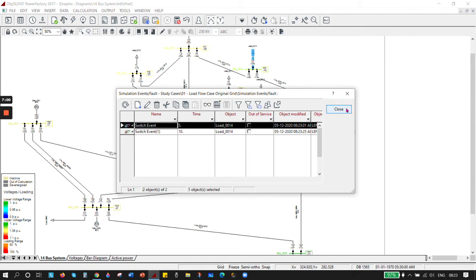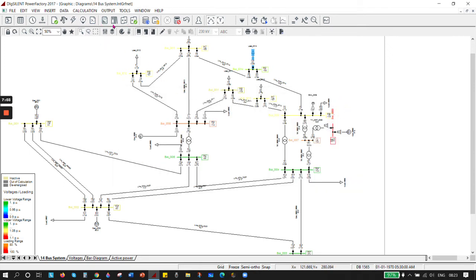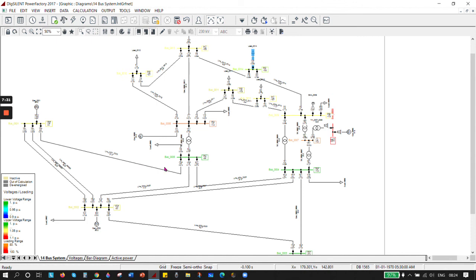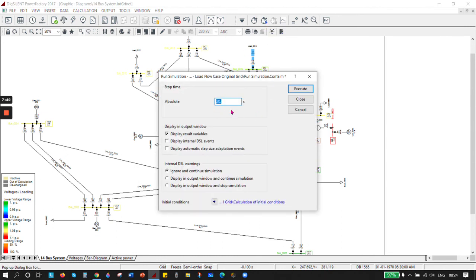You can check that the events you added are listed correctly - a switch event and a close event. Press OK. Now run the load flow again to initialize everything. Once the load flow is run, calculate the initial conditions and press Execute. If the load flow is balanced, the process will execute. Otherwise, a pop-up will say the load flow is not converging - then you need to check each bus: line flow, bus voltage, transformer ratings, and so on. Once everything is correct, start the simulation for 20 seconds and execute.